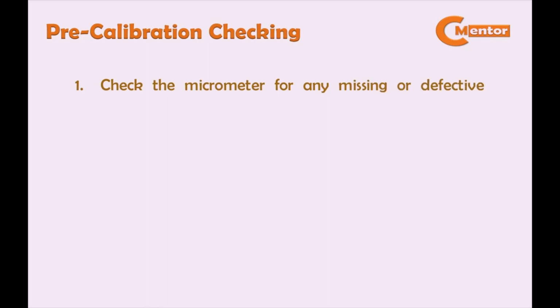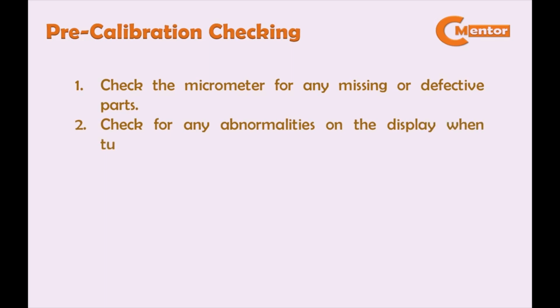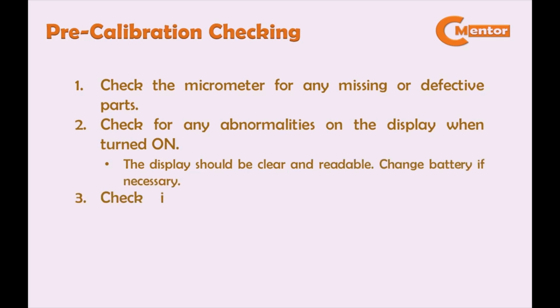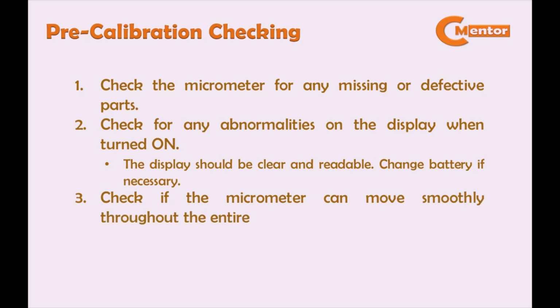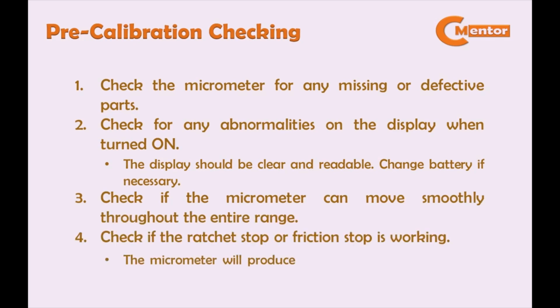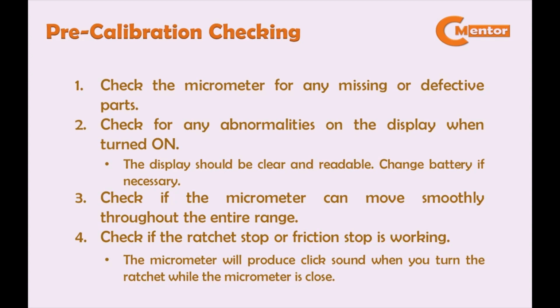After preparation, we need to undergo pre-calibration checking. First, check the micrometer for any missing or defective parts. Second, check for any abnormalities on the display when turned on. The display should be clear and readable. Change the battery if necessary. Third, check if the micrometer can move smoothly throughout the entire range. Fourth, check if the ratchet stop or friction stop is working. The micrometer will produce a sound when you turn the ratchet while the micrometer is closed.